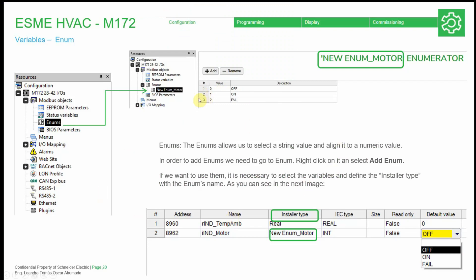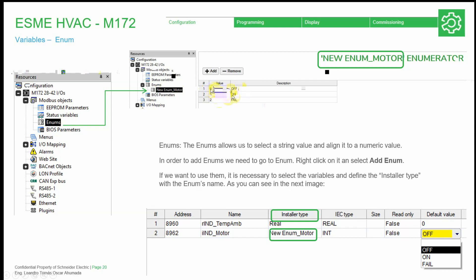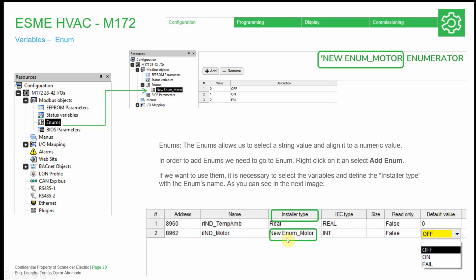Something important here is the enums, which allow us to have a string value instead of a numeric value. It is much simpler to identify and read the program. For example, if we right-click and add an enum — in this case a motor enum with these variables — when the value is 0 we see 'off', when it's 1 we see 'on', when it's 2 we see 'fail'. In the status or EEPROM, when we define the variable type, we define it as the enum instead of integer or real, and the default value shows the string value instead of 0, 1, 2, etc.